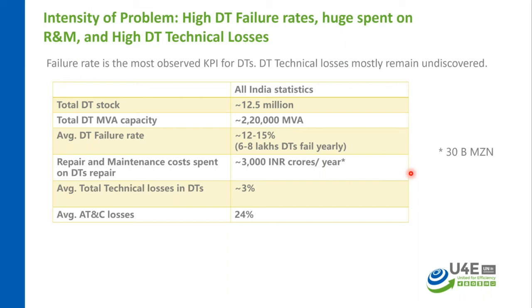The DT failure rate in India is higher, mainly after 100% electrification has been done, because of the overloading, which is happening because of intermittent loads coming through theft and unmetered connections. Also, poor asset management is one of the important reasons. As a result, the failure rate is 10 to 12%. The definition of failure here is that any transformer deviating from the performance in the utility specification while in working condition is called a failure, which may include oil leakage, bushing damage, and many other things.